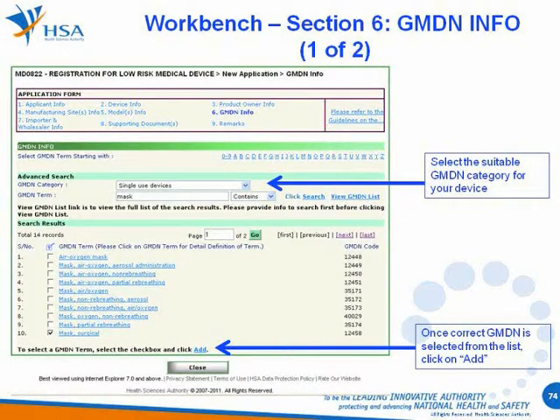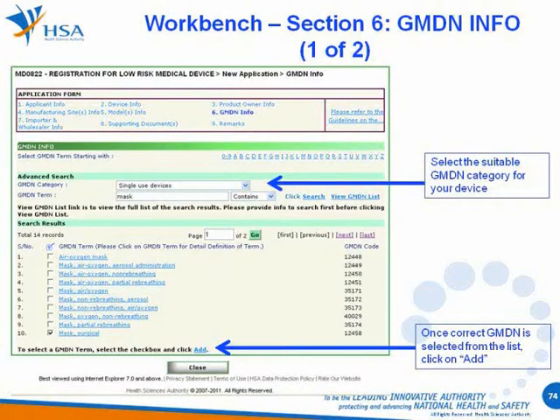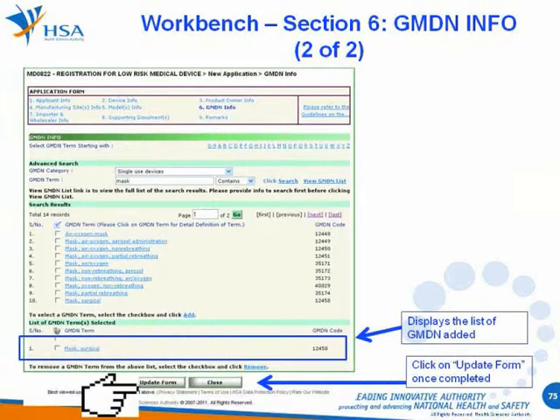For Section 6, GMDN Information — GMDN stands for Global Medical Device Nomenclature. You will need to select the suitable GMDN terms to describe the device in this application. Select a suitable category from the drop-down list, then you may wish to enter a GMDN term field before clicking on the Search button. A list of related GMDN terms will be populated. Choose one or multiple GMDN terms from the search results. Once the correct GMDN is selected, click on Add. You will not be able to create new GMDN and can only choose from existing GMDN lists preloaded into the system. Click on Update Form once completed.